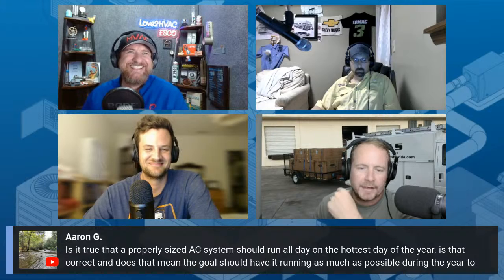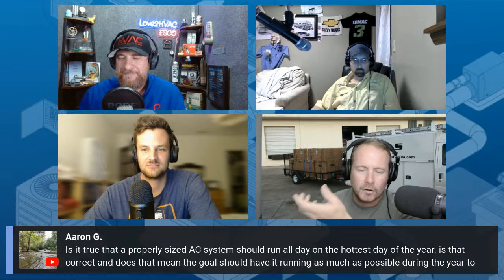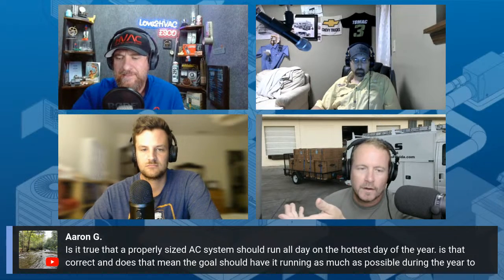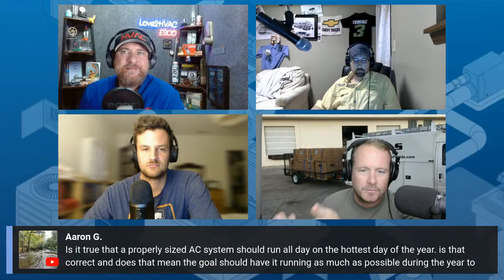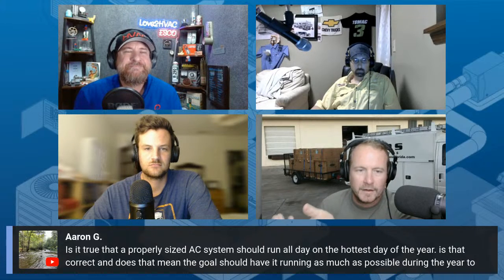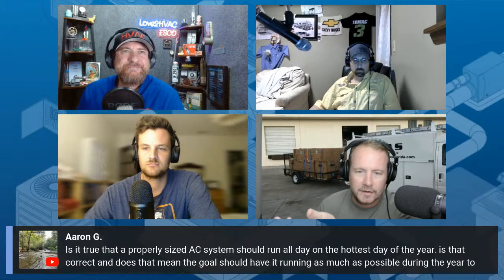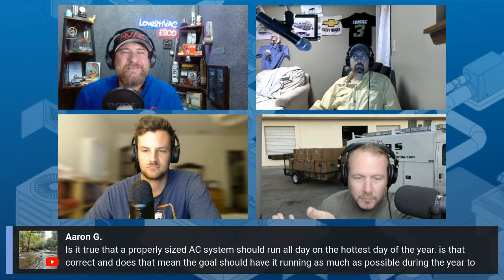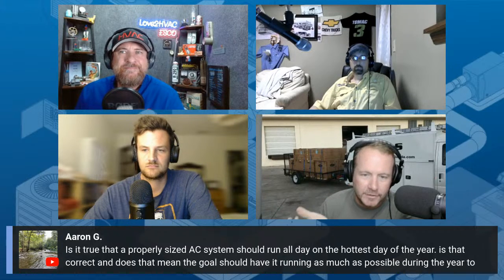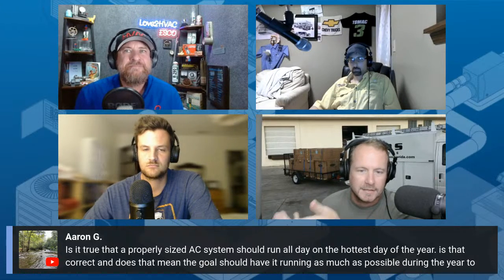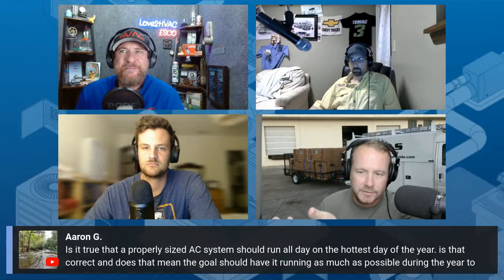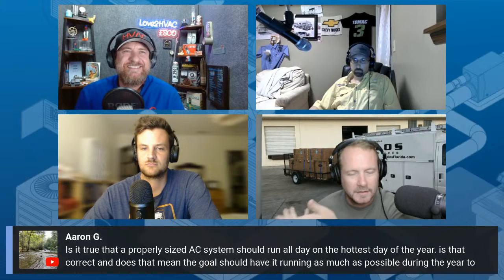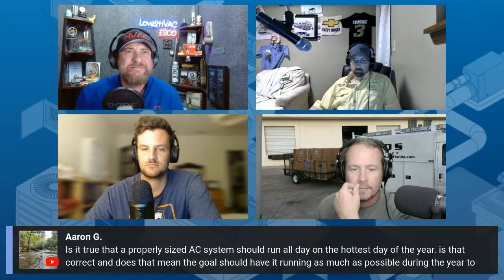I'd also add, it really depends on your market. There are dry, arid markets where oversizing doesn't have a humidity consequence, so you can get away with it a bit more there. But even then, oversizing has an energy consequence regardless of whether it has a dehumidification consequence. So we do not want to be oversizing equipment, at least not radically, for both reasons.